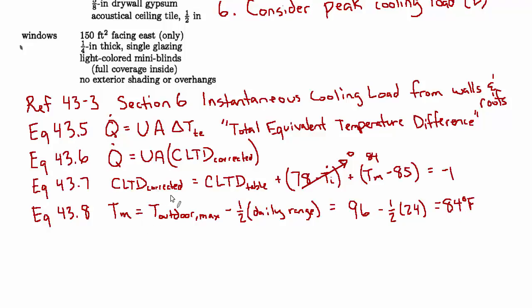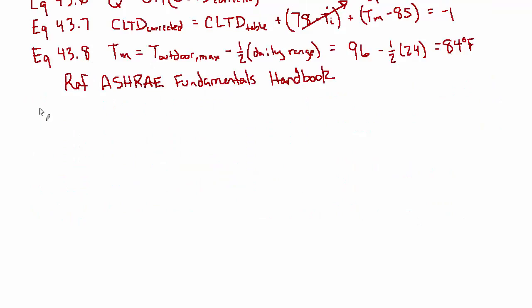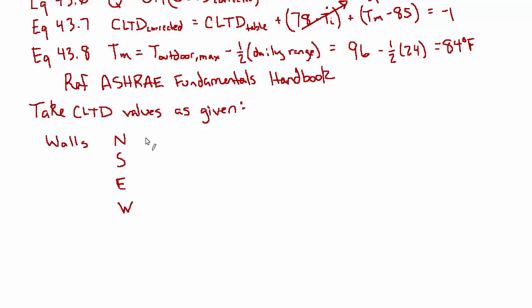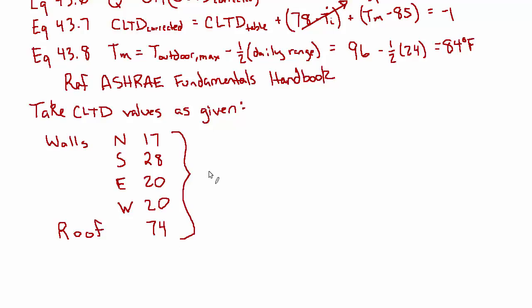If you did have to do the lookup, you'd use the ASHRAE Fundamentals Handbook. In our case we take them as given. For the walls: 17°F delta-T for the north, 28°F for the south, and 20°F each for the east and west. For the roof we have 74°F — a very large number — and of course these are all delta-T values with units of degrees Fahrenheit. With that, we're ready to look at the walls and work out the overall heat transfer coefficient.